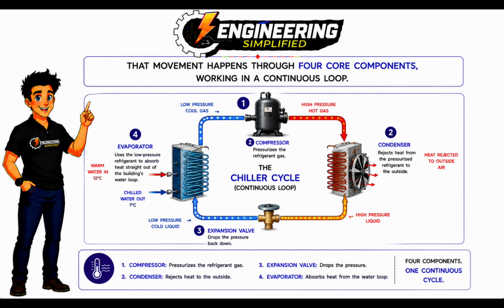That movement happens through 4 core components working in a continuous loop. The compressor pressurizes a refrigerant gas. The condenser rejects heat from that pressurized refrigerant to the outside. The expansion valve drops the pressure back down, and the evaporator uses that low-pressure refrigerant to absorb heat straight out of the building's water loop.